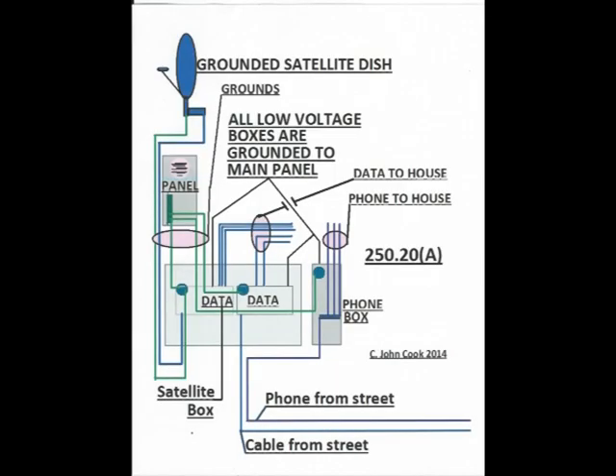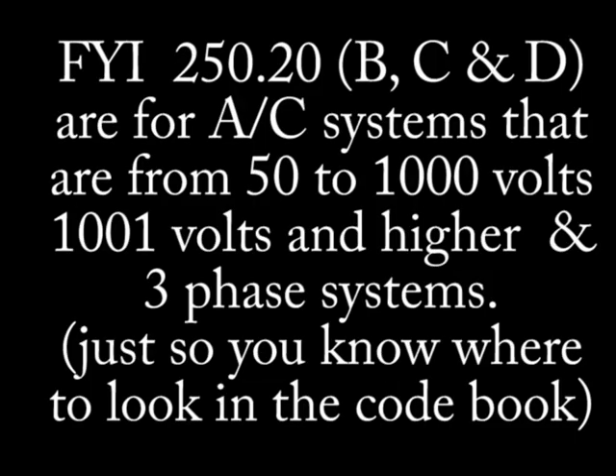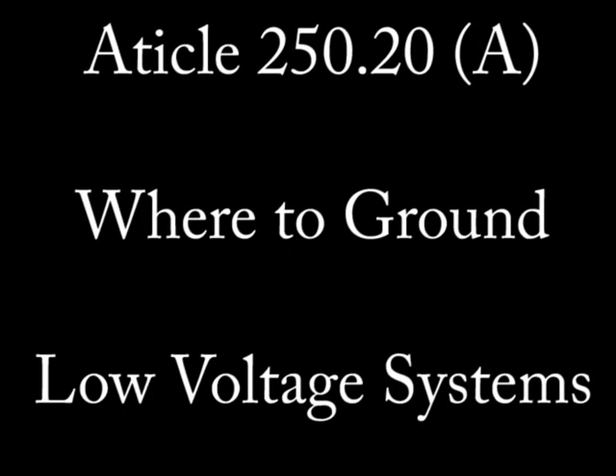That just about covers what alternating current low voltage systems need to be grounded and where to ground them, as shown in the diagrams. That really is the heart of article 250.20 part A. For alternating current systems with voltage that is nominal or over 1,000 volts, then parts B, C, and D cover that area, but it is very vague, just like part A is. That is why I provided the diagrams so there would be no doubt about what this article is covering and where to look in the codebook for data and communication system grounding.